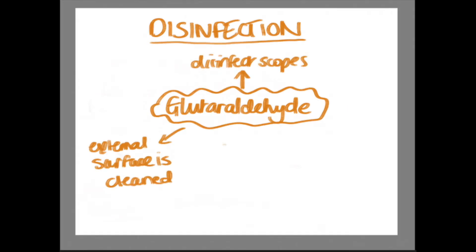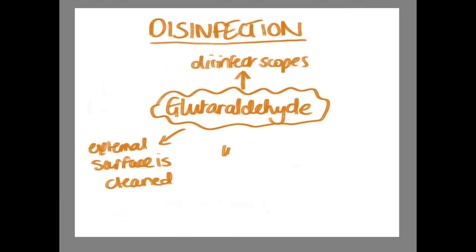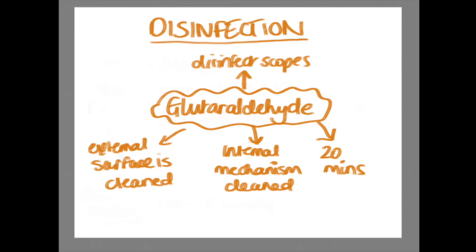Generally, the external surface is cleaned and visible debris are removed. The internal mechanism is flushed with detergent and the endoscope is exposed to glutaraldehyde. The minimum exposure time is around 20 minutes, followed by rinsing of the glutaraldehyde.